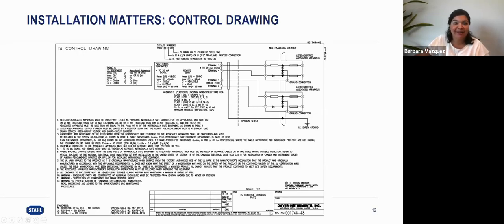Yeah, that's why. If your hazardous area is a group B, then you wouldn't be able to use this field device. So again, that's very important to know the entire classification of the hazardous area. The control drawing will spell out exactly where you are allowed to install it. In this case, it shows the barrier that you need to use, how many, and all the notes letting you know some of the rules you need to follow for the entity parameters and the values, which we're going to be talking about in a little bit.